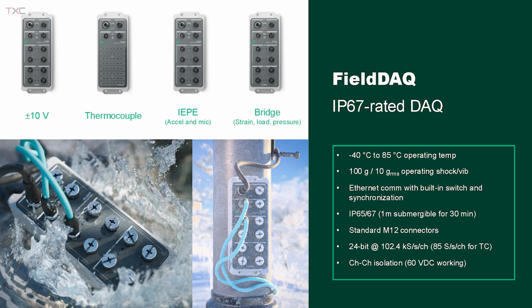They're all 24-bit. With the exception of thermocouple, they're all 102.4 kilosamples per second. So this uses one of those delta sigma converters like we were just talking about. So you can set the rate. There's several different clocks to choose from, but you can basically call your own rate. And then any channel on the same device or any channel between devices that are on the same network are going to synchronize within 1 microsecond.